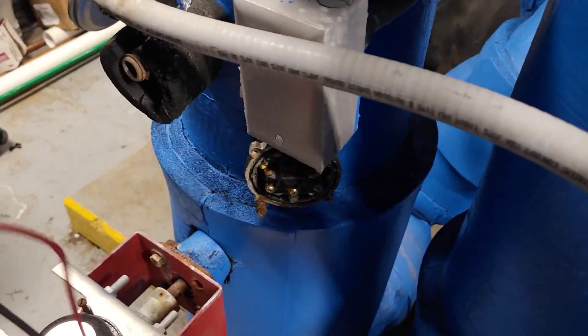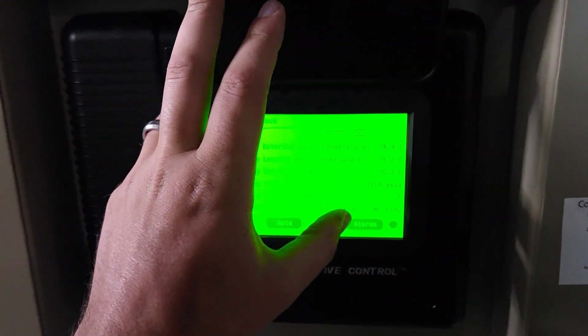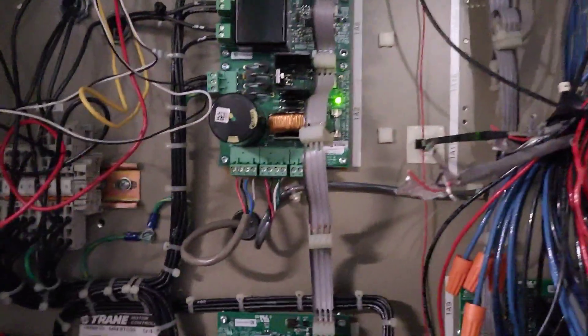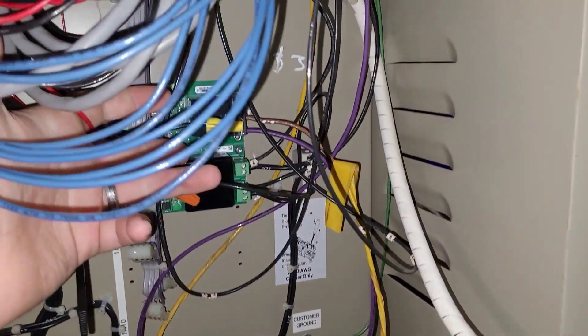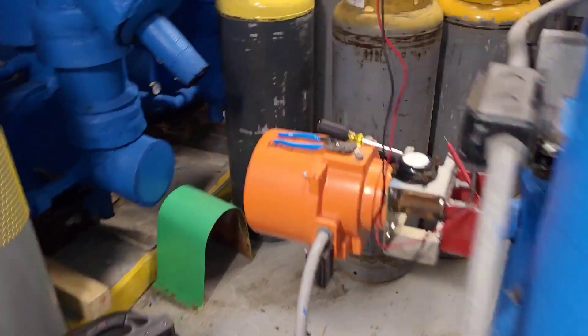Okay, according to that we have continuity across it. We're still showing no flow. That could be an issue. All these are brand new though. I'm thinking it was this one down here. I hope we don't have a com card failure. That's not going to be good.